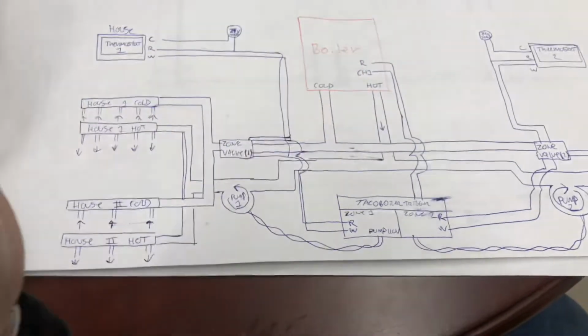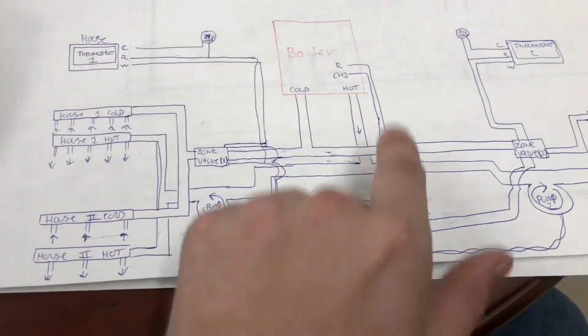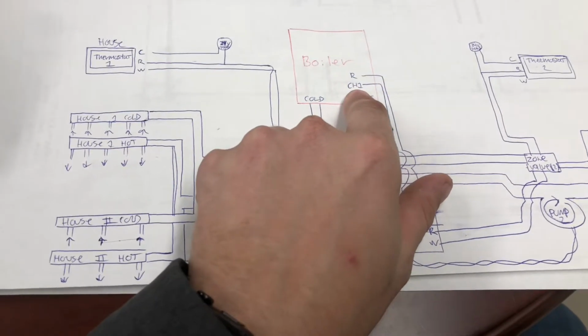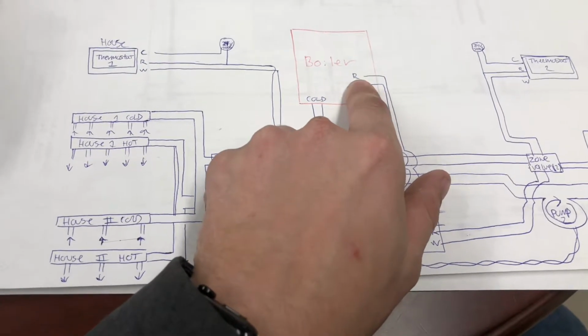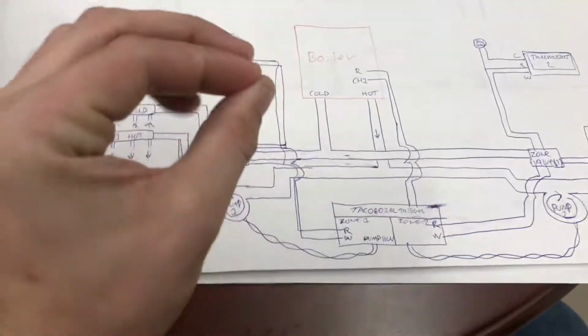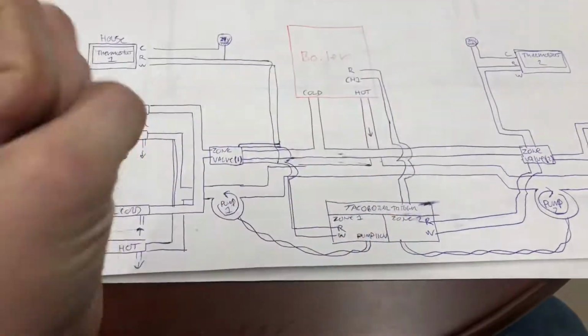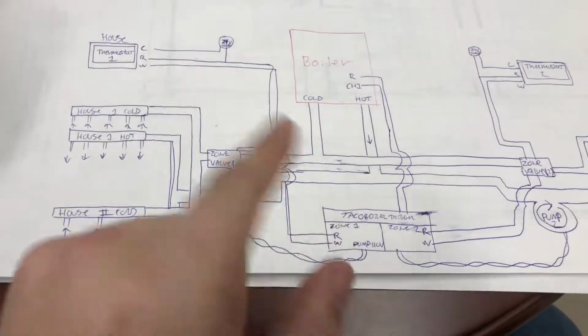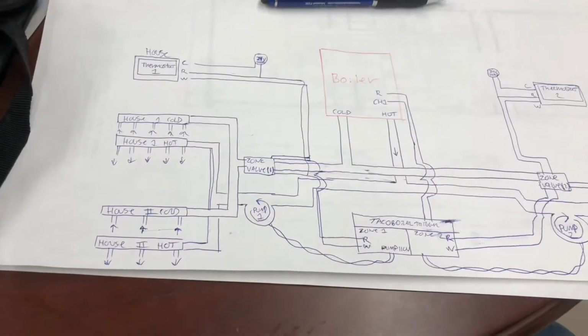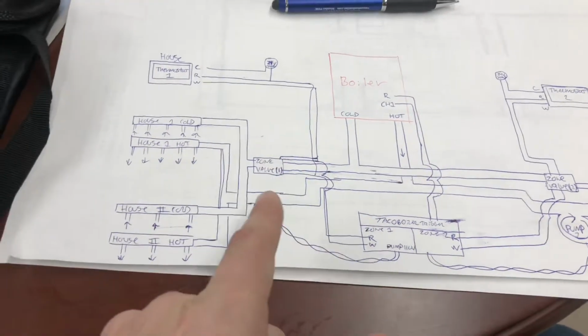It'll open up this zone valve, which is just a spring-loaded electro valve, and then it'll also trigger the channel 1, which is the W signal, and it'll ground that to the R. All R's and all circuits here are going to be wired together. So if something's not working, make sure that's the case. But again, same for the garage as it is for the house. It's a pretty simple circuit, but that should do what you need.